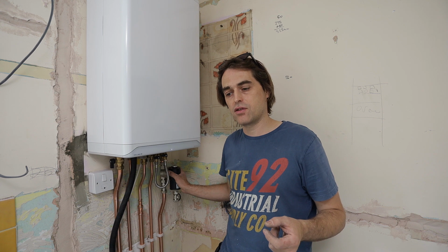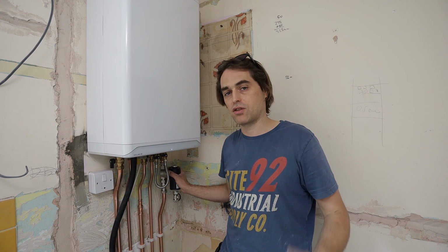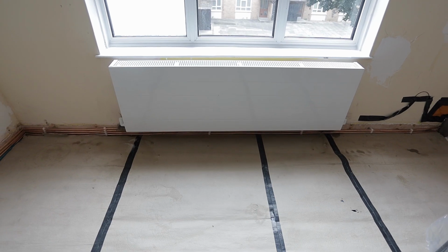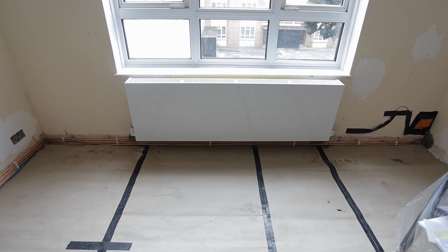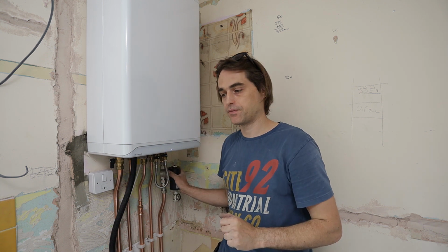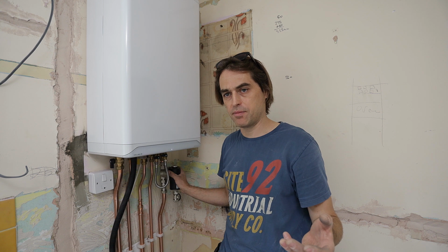So I've installed oversized radiators on this job. I installed the biggest radiators I could get under the windows. And that way we'll be able to run this boiler at temperatures around 50-55 degrees flow when it's -1 outside. So almost like running a heat pump. So this boiler will be extremely efficient on central heating.